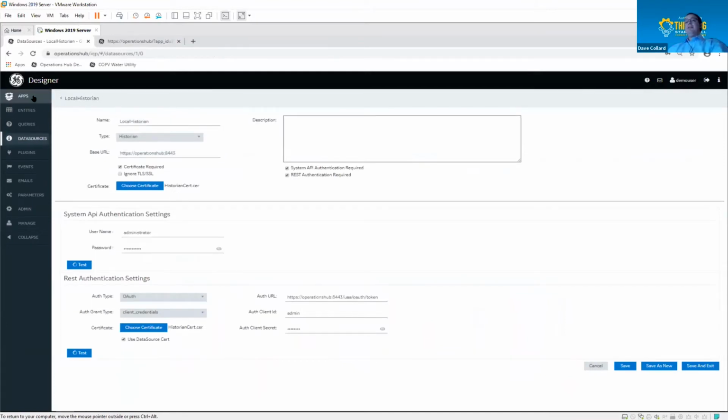If you have more than one historian, which a lot of our customers do, we can connect to more than just one historian. So we allow you to have several connections to the historian. There's actually no upper limit to the number of connections to historians in the product. So if you had, say, 3, 4, 5 historians spread throughout your facilities or multiple facilities, you can use this to be a data aggregate. This visualization tool can aggregate all of those historians together from one common platform.